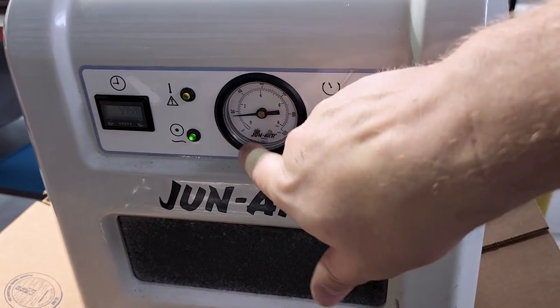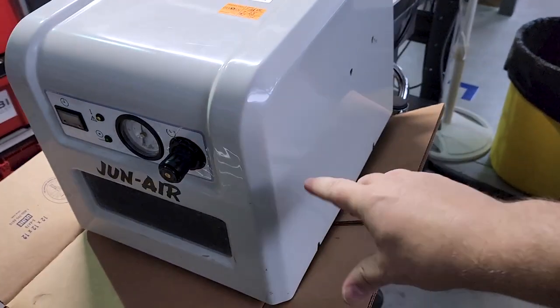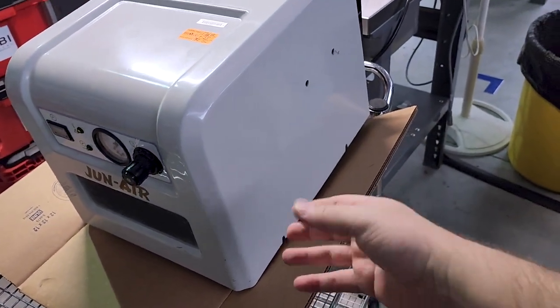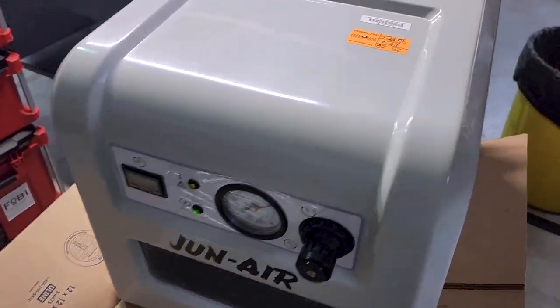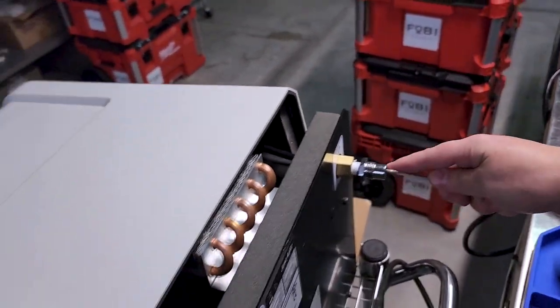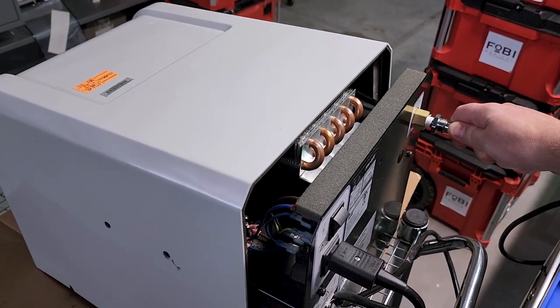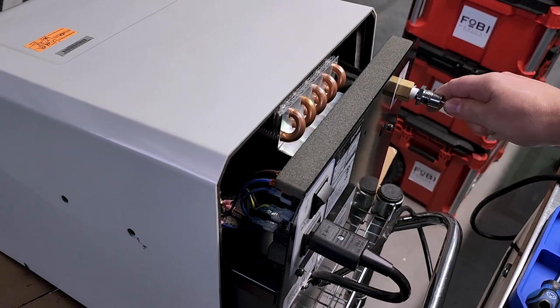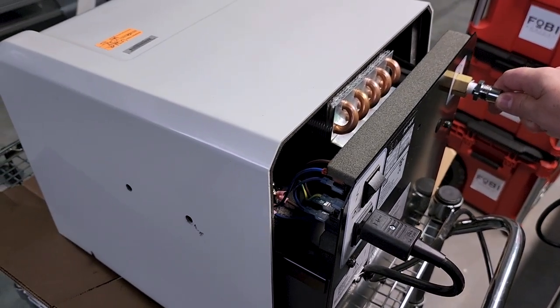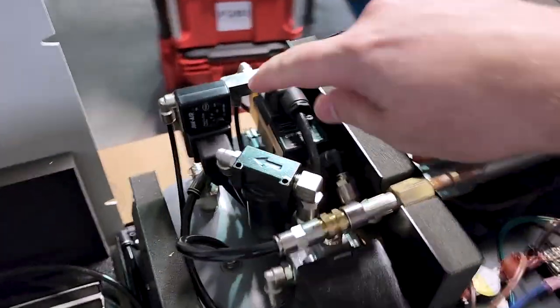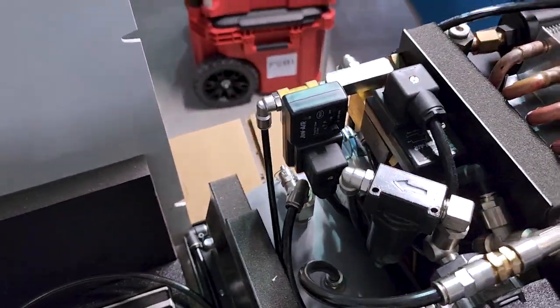See, we have power. This is air light indicating a problem. So you notice how it wasn't venting or it wasn't building pressure. It was venting internally to a drip pan, which is located underneath. You can see it down there. So it purges the moisture from the tank for a certain duration. And then it goes to that tank in the bottom and then it starts building pressure and it builds pressure quickly and quietly, which is its job.